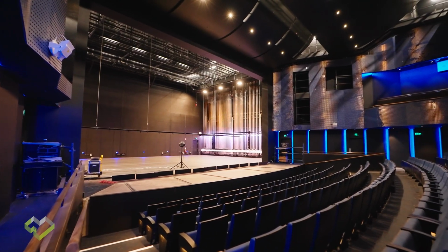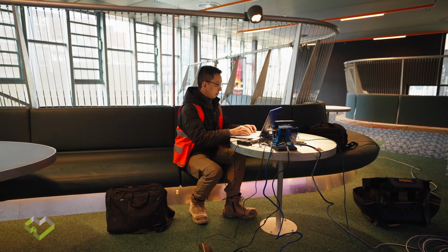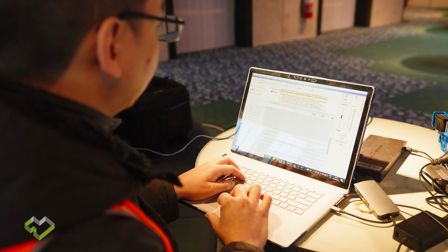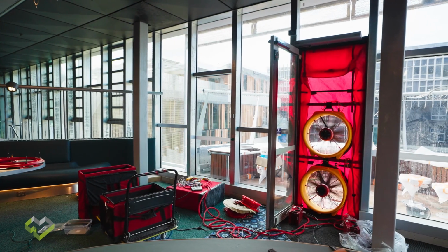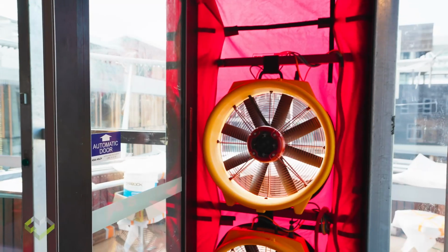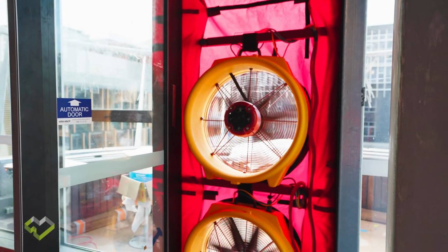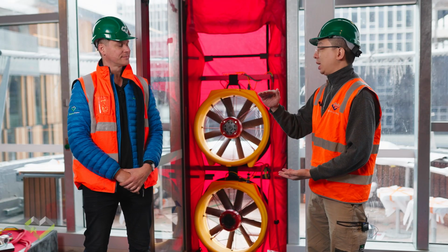What does that mean? An air tightness test is a procedure where we use fans to pump air into a building to elevate the building to a standard pressure. Typically it is 50 Pascal. If you are in the US, you may use a different standard, elevating to 75 Pascal.